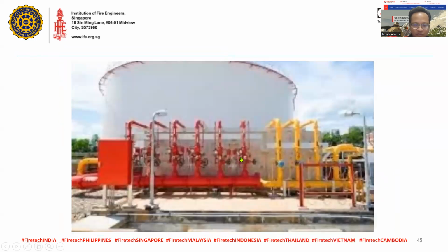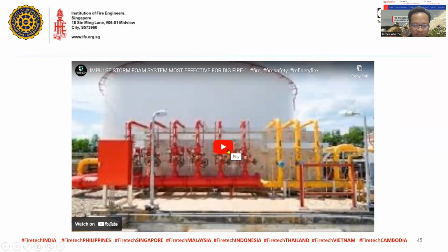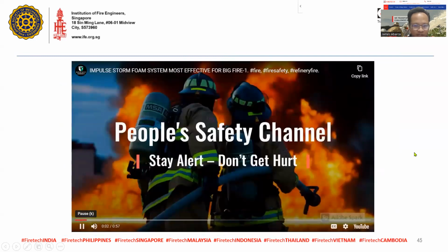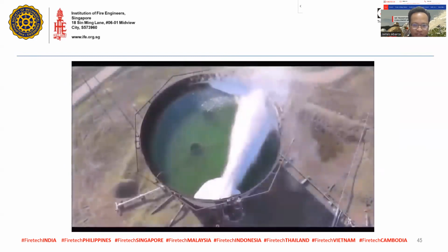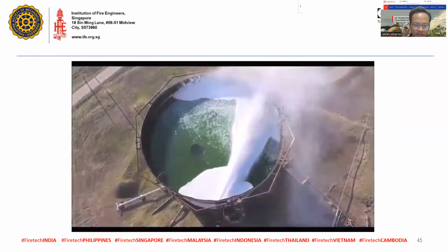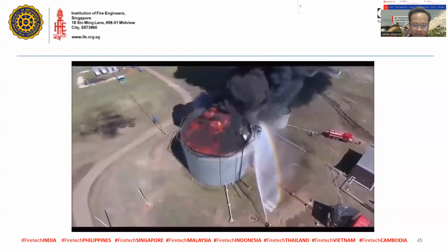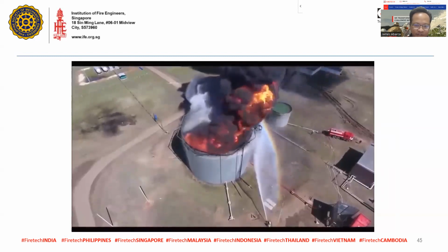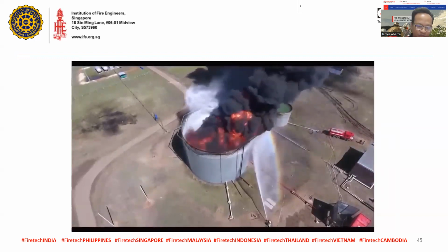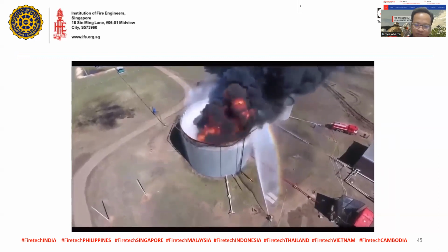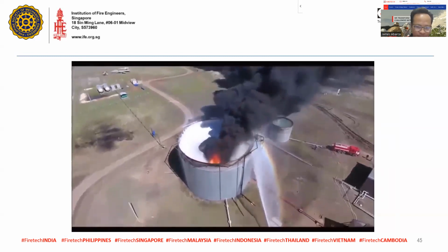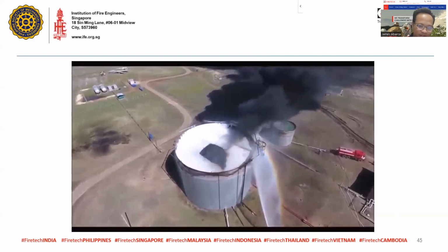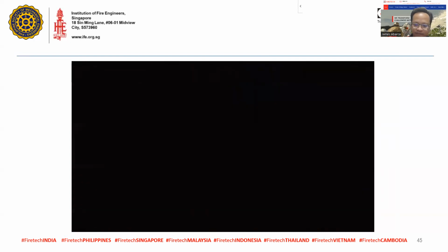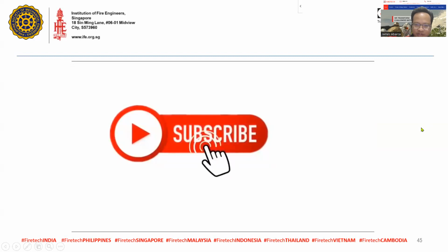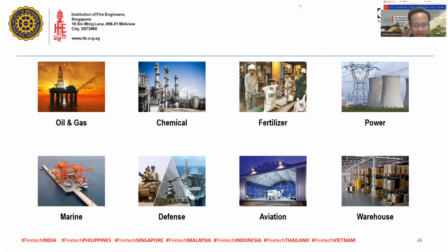For foam suppression, here's a video that would give us an idea, okay, how this system is being applied, where it is being applied from this test of fire that they have. So imagine this is a very huge container of flammable liquid in a petrochemical or in a chemical industry, and this is an actual fire. Okay, so fire is always on the surface of the fuel, so when foam is being introduced, it will blanket off the fire, thereby separating it from air, no more oxygen. Okay, that's how foam suppression works. So it is applicable on oil and gas, chemical plants, fertilizers, power plants, marine defense, aviation, and warehouses.